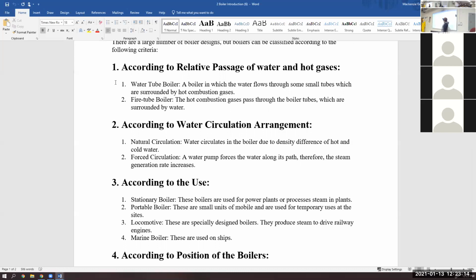In a fire tube boiler, you have hot gas in tubes surrounded by water. In a water tube boiler, you've got water in tubes surrounded by hot gas. At Plant Miller, the picture they showed us, was it a water tube or a fire tube boiler? Water tube. Exactly.